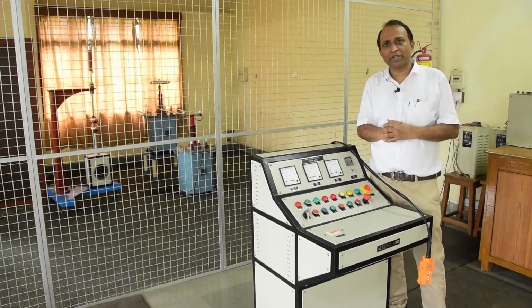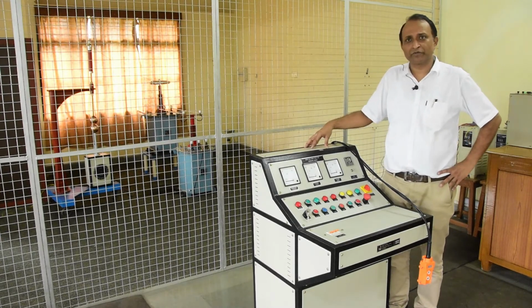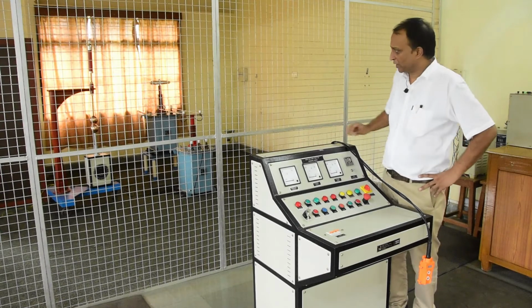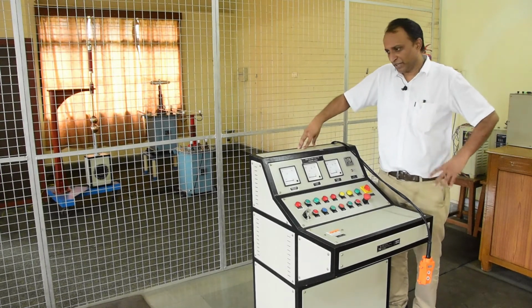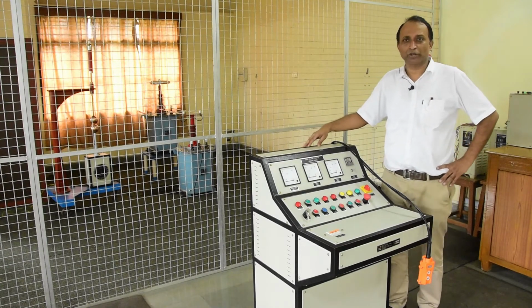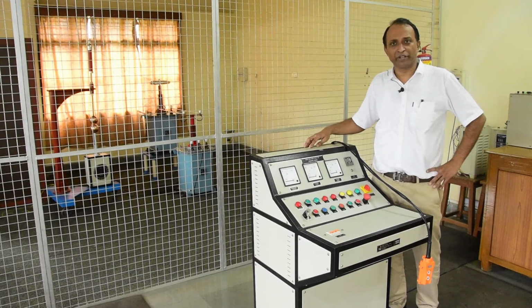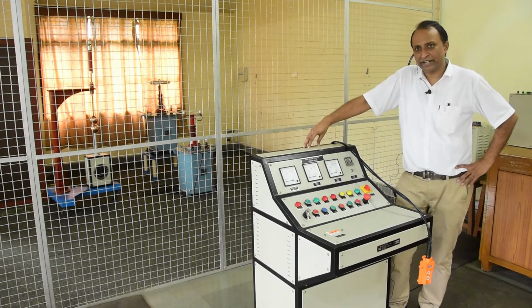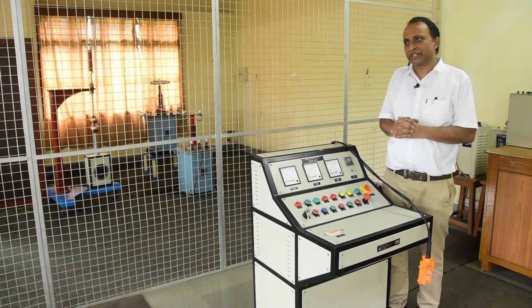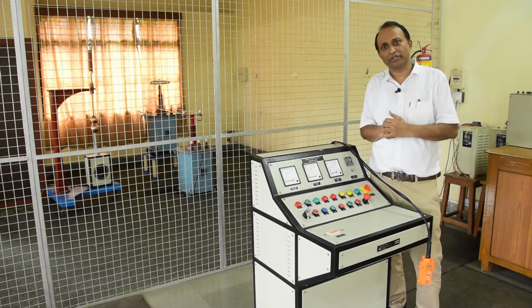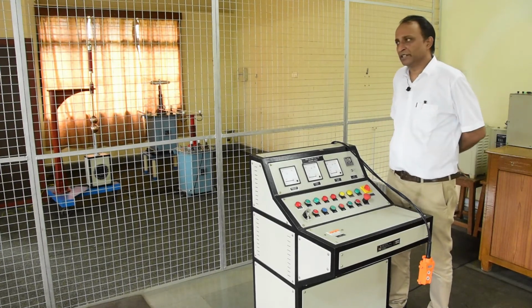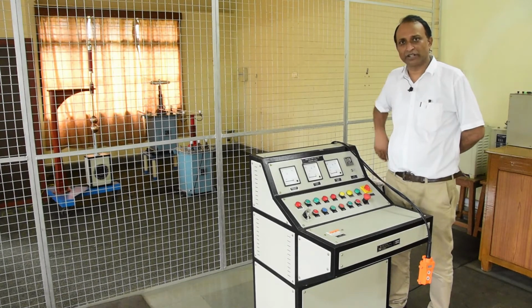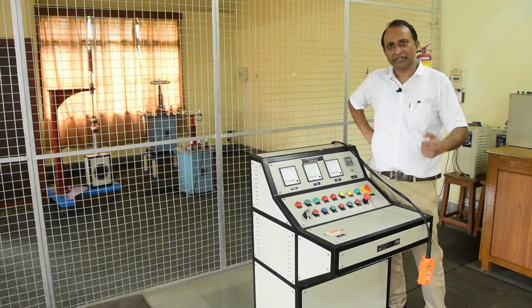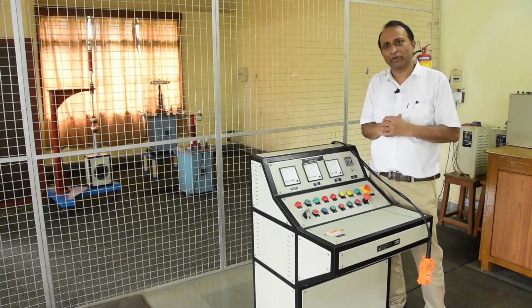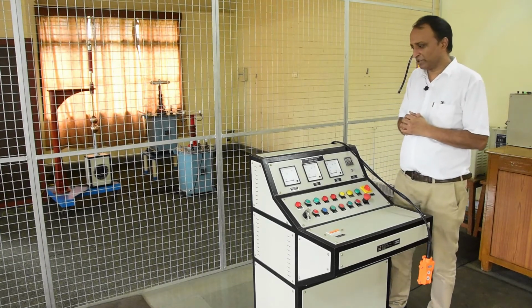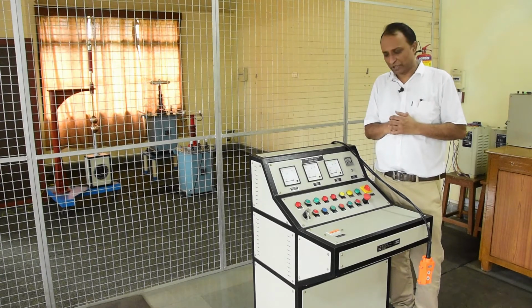But at the same time, if we are supposed to measure the voltages normally experienced in the testing of insulators in high voltage laboratories, like impulse voltages or high-frequency transient voltages, and also lightning overvoltages, right? All such voltages, even DC or impulse voltages induced across the power system and transmission line insulators due to overvoltages, require special measurements. Consequently, there has to be calibration of voltmeters for measuring such impulse voltages.